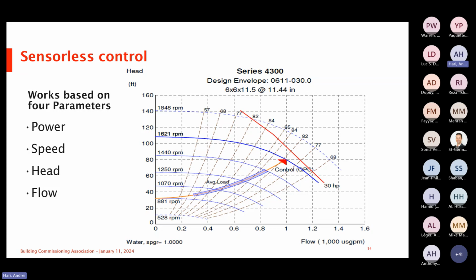If you look at the load on the shaft, and you've got variable torque, the motor will only draw the power required based on the resistance, or the load, on that shaft. So if that 200 horsepower motor only has 1 horsepower worth of work to do, or no load on the shaft, it's only going to draw 1 or 2 amps. And as the load or the resistance on that shaft starts to increase, the amount of power being drawn to overcome that resistance starts to increase.